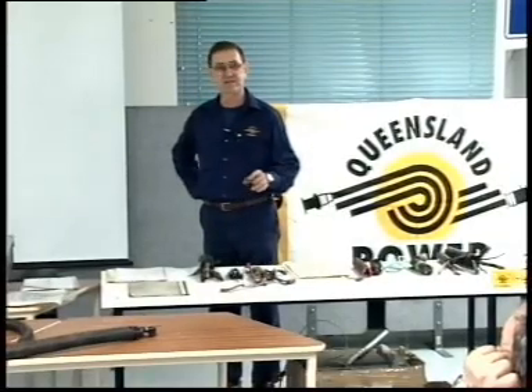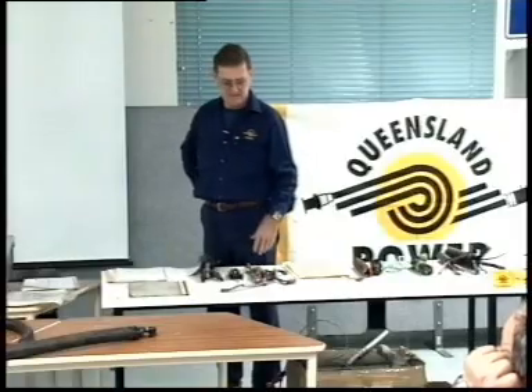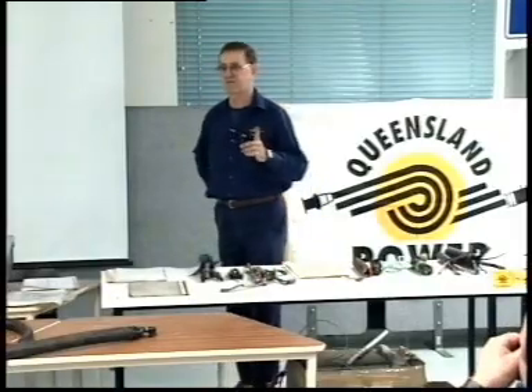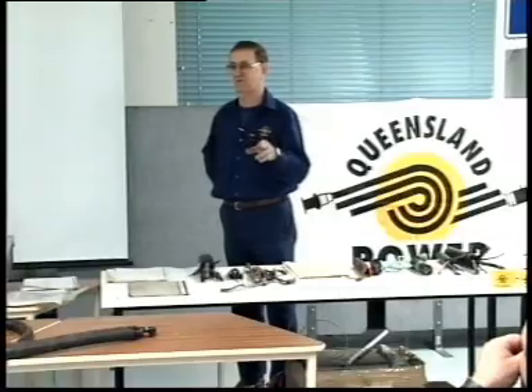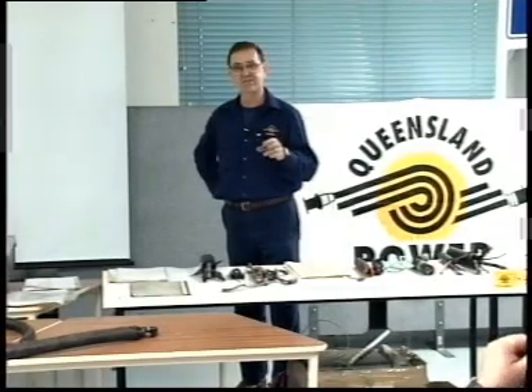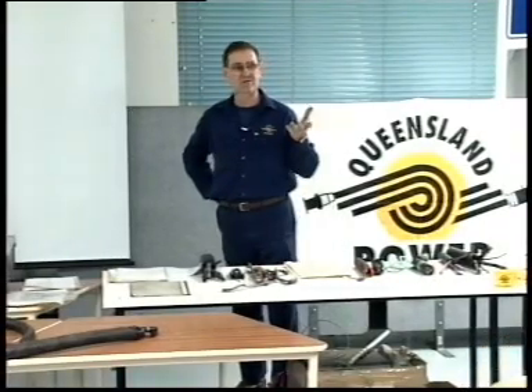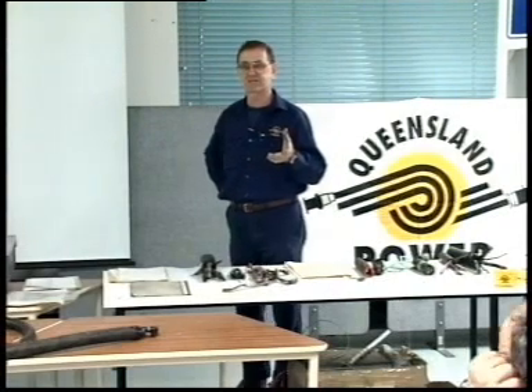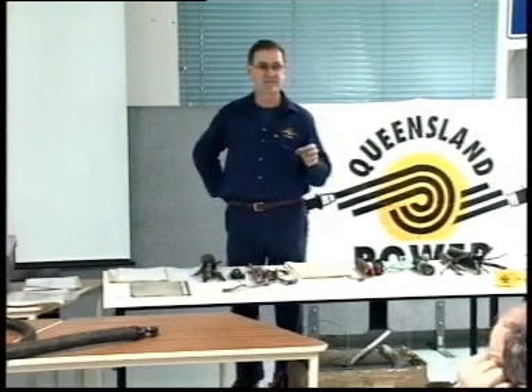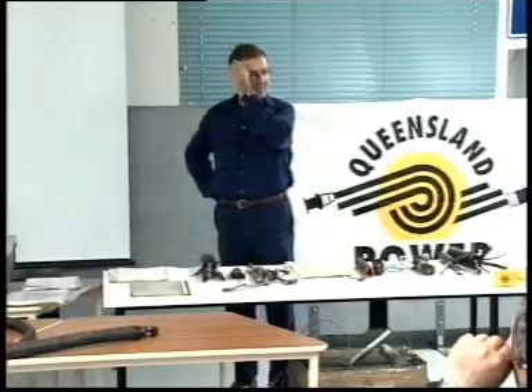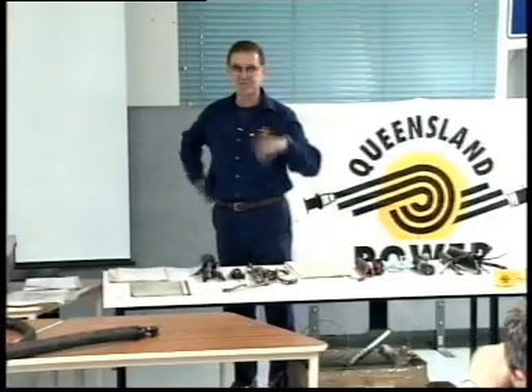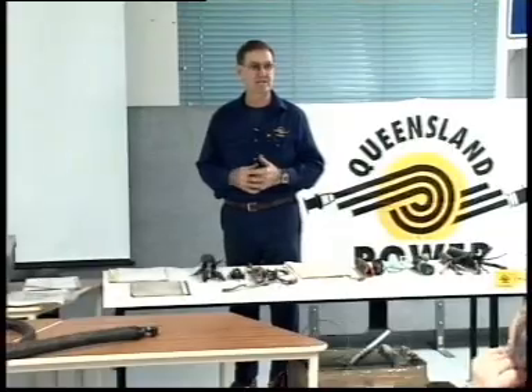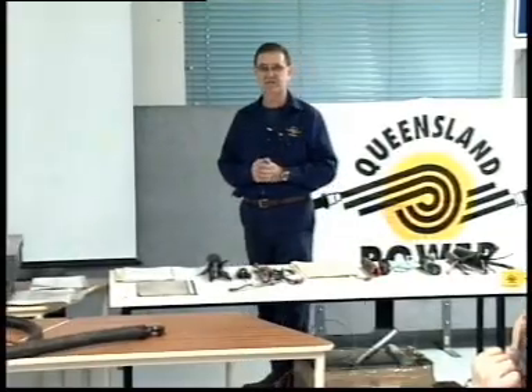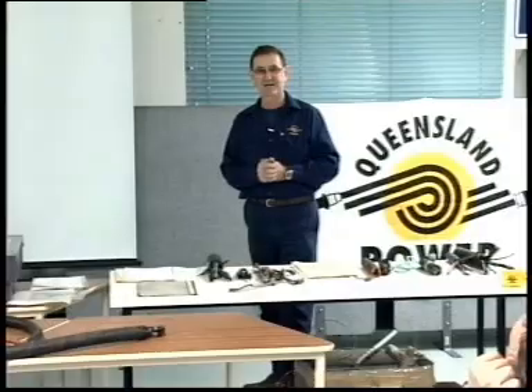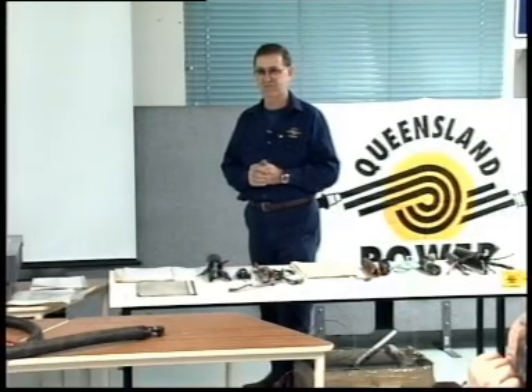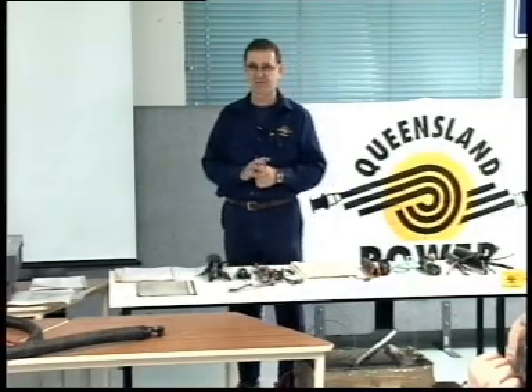Now, if any of the earths get broken in these cables, you can still have a single earth wire, for instance, still connected to your machine, so you have an earth down there. The only problem is the other earths build up voltage in them due to the induction from the other phases that are in there. So you can have a rise of potential on the actual frame of the machine, particularly on shuttle cars where we've got rubber wheels. But we have to do a test to maintain, within the Australian standard, that we have enough earths in the system to be able to carry the fault level down there.